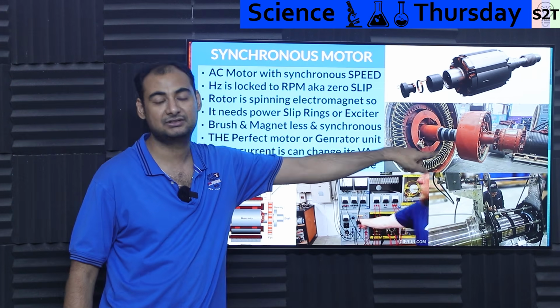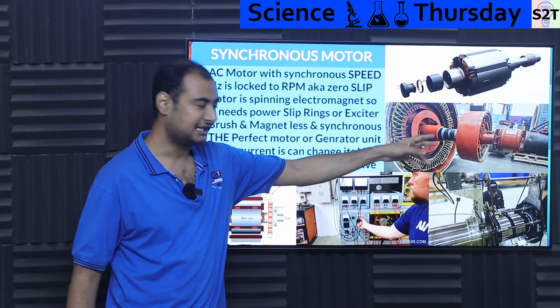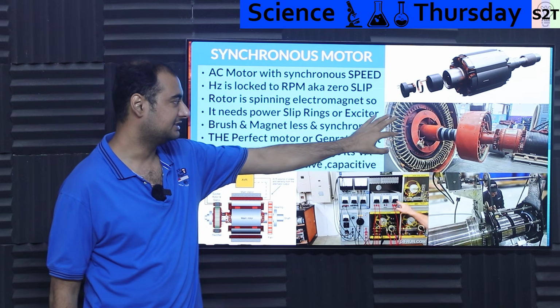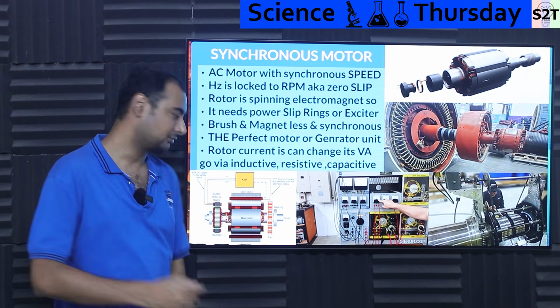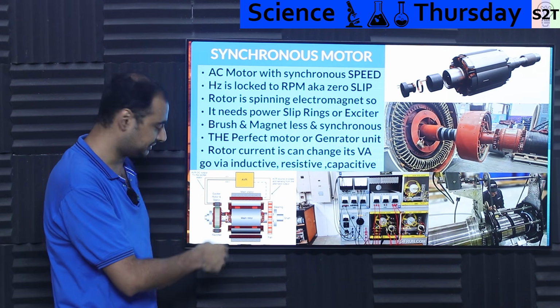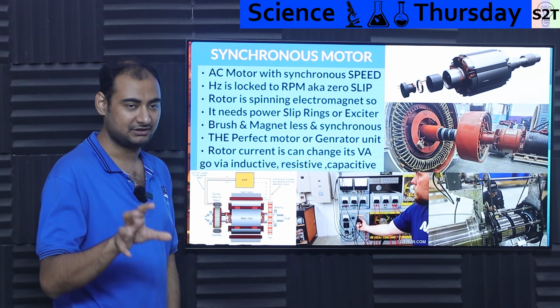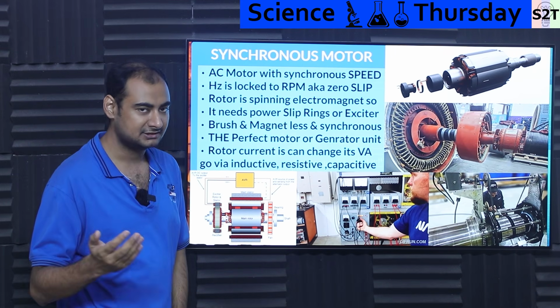Then, since it's AC but you need a DC electromagnet here, what you do is use what we call a spinning diode. A diode takes the AC, converts it into DC, and tada. And again, you still have the same control, because here you can have auto voltage regulation, you have a control system deciding how much you have to do. Does it work? Absolutely, very flawless system, does work.